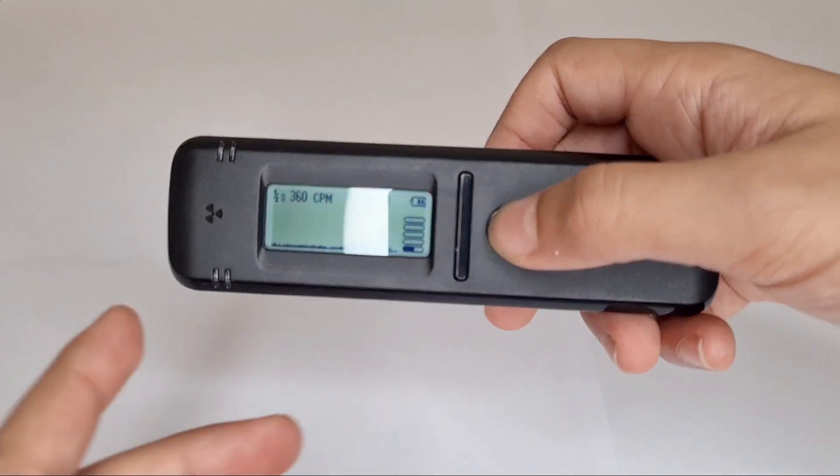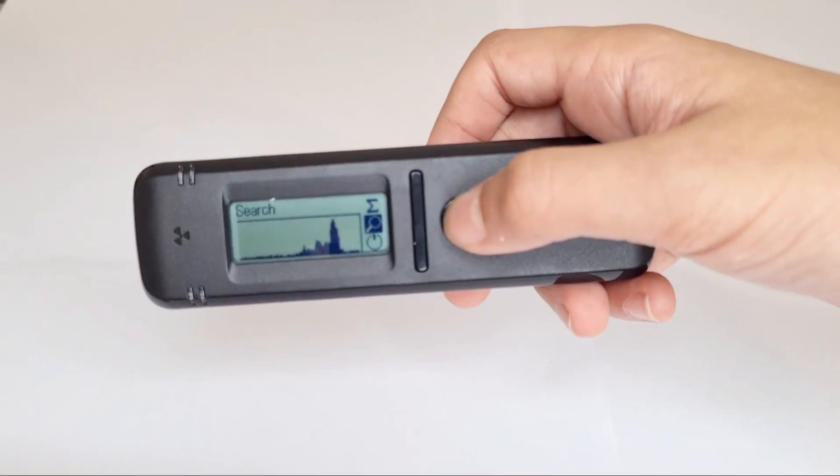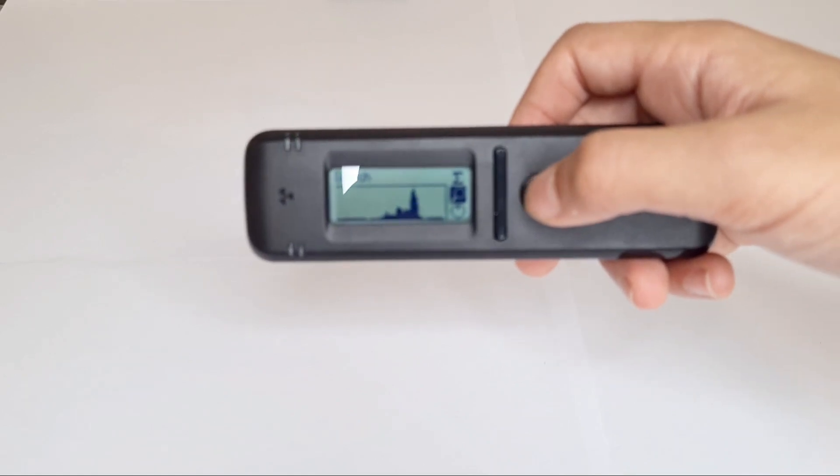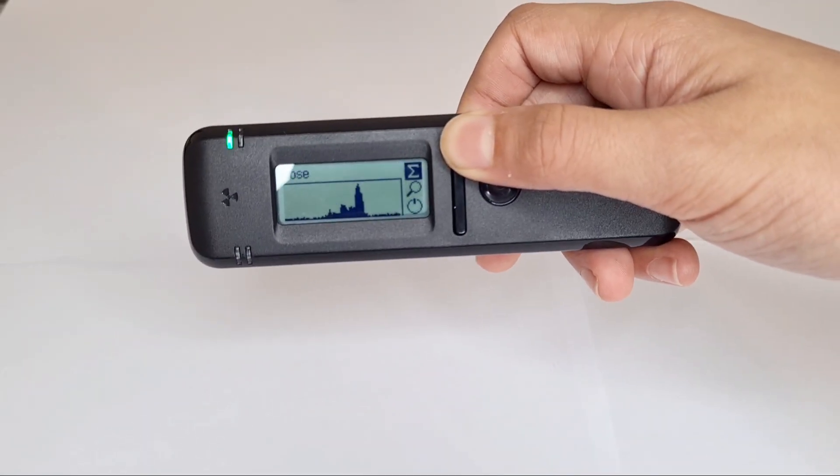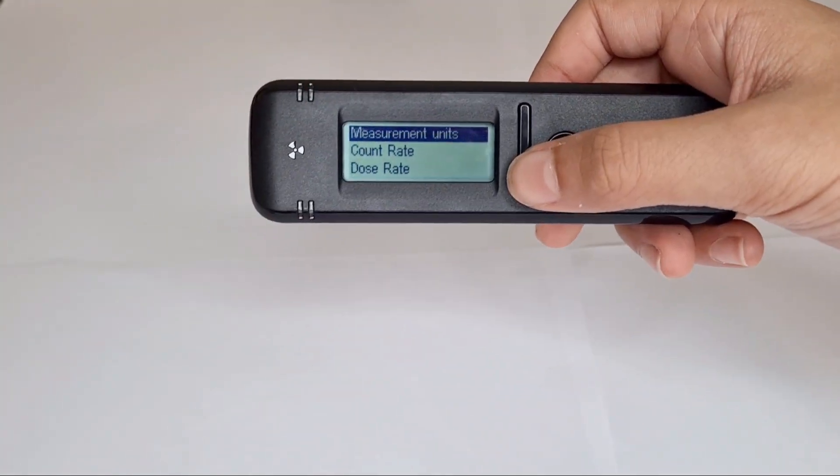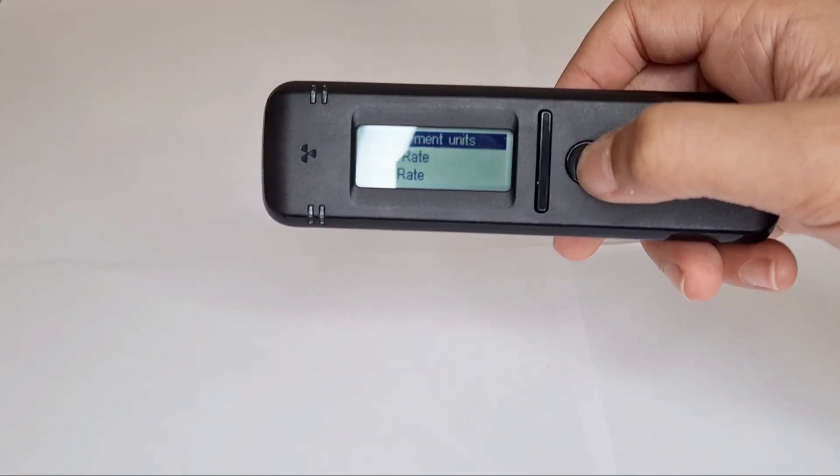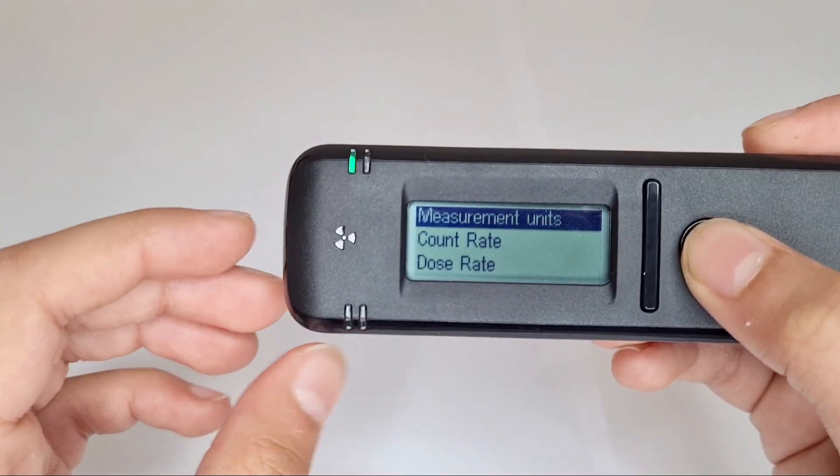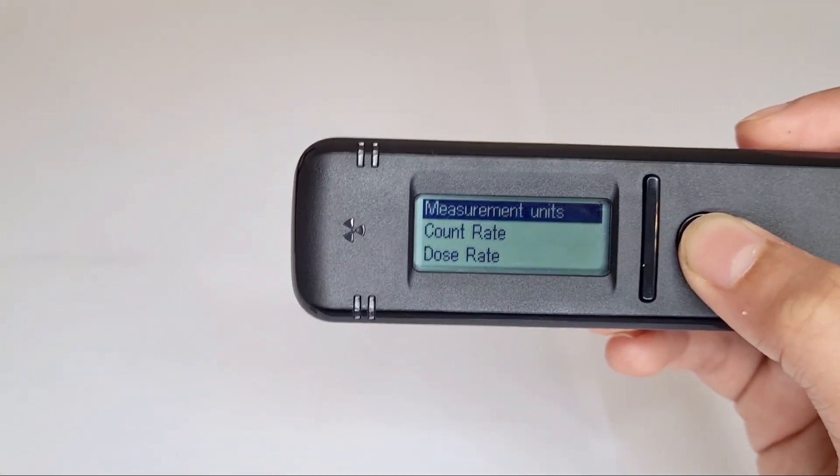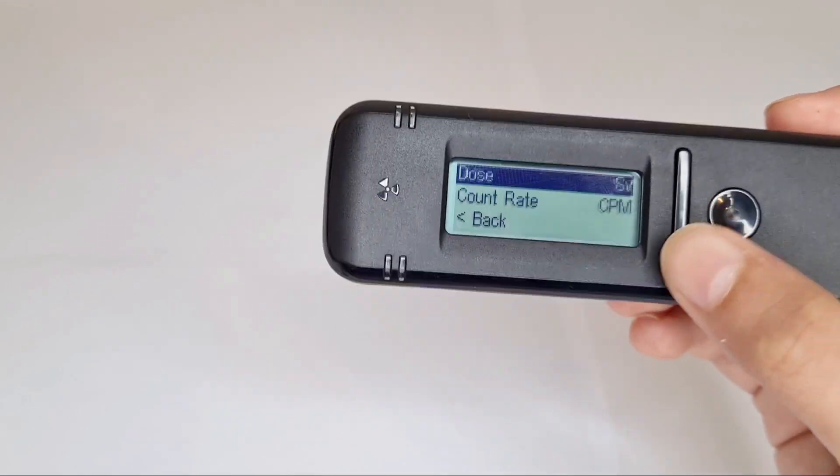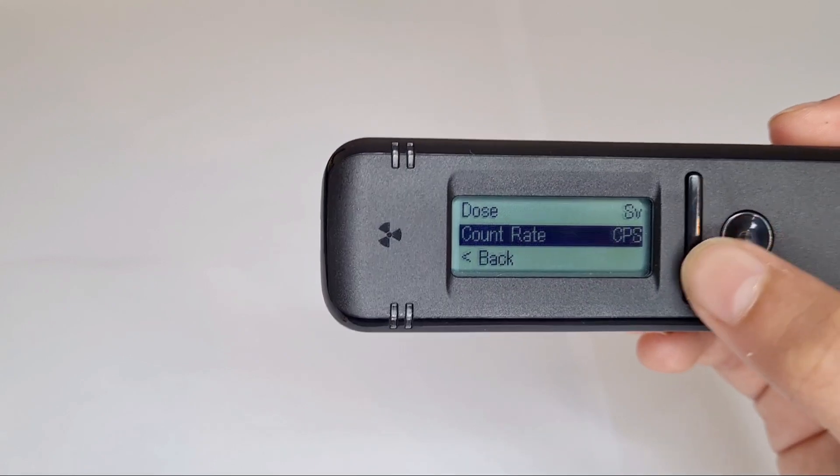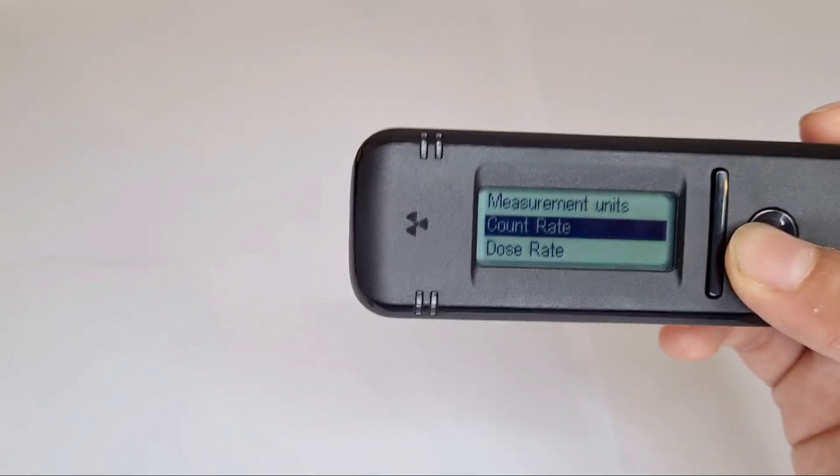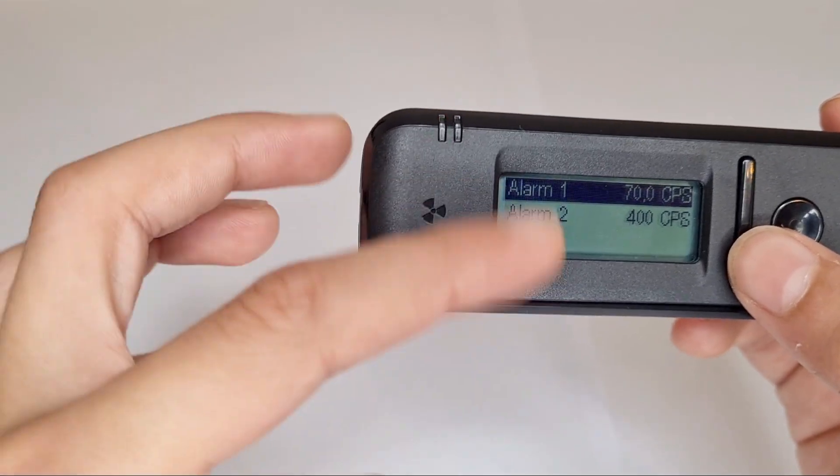Then what else you can do, you have to turn this. You go to settings here. You can adjust the measurement units, dose sieverts or roentgens. I'm going to keep it on sieverts. Count rate CPM or counts per second. I'm going to keep it on counts per second for now. Counter alarms, you can adjust how high you need stuff to be for the alarm to go off.